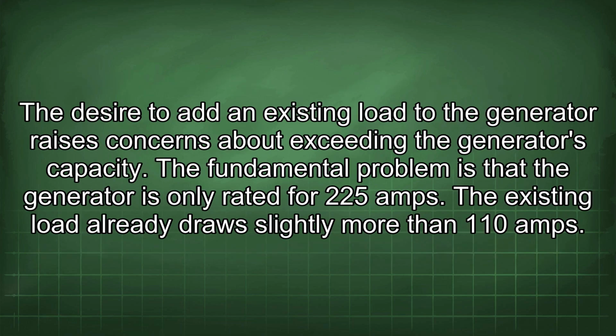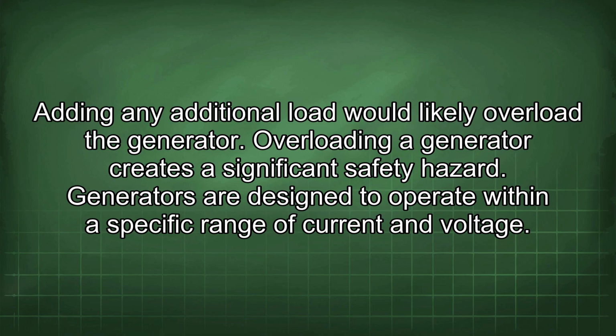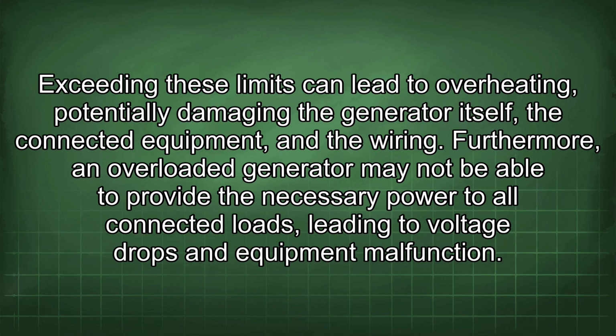The desire to add an existing load to the generator raises concerns about exceeding the generator's capacity. The fundamental problem is that the generator is only rated for 225 amps. The existing load already draws slightly more than 110 amps. Adding any additional load would likely overload the generator. Overloading a generator creates a significant safety hazard. Generators are designed to operate within a specific range of current and voltage. Exceeding these limits can lead to overheating, potentially damaging the generator itself, the connected equipment, and the wiring.